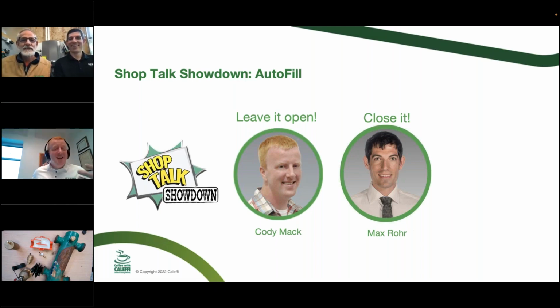No, I'm just teasing. The fact is that you got to be able to fill that system up with water when you're doing that stuff, getting rid of dirt and debris through a dirt separator and air through the air separators. You got to keep that valve open. The only time I would highly recommend closing it is if it's a property that's not continually occupied, like a vacation property that you're not at all the time. That might be a good one. But if it's a primary residence, you're there all the time, chances are if there's a big leak somewhere, you're going to know it.